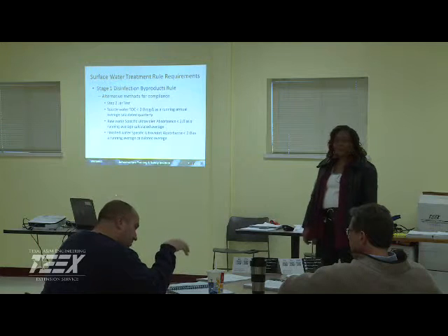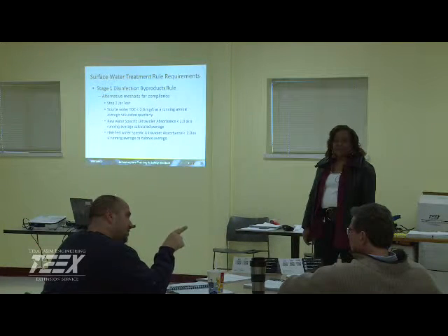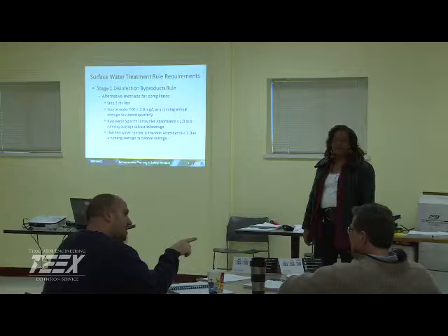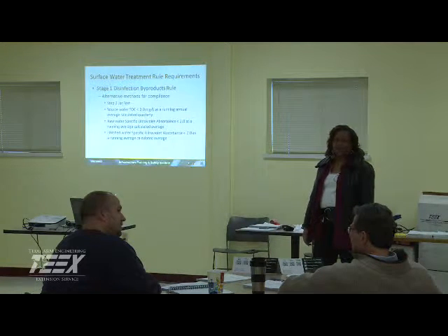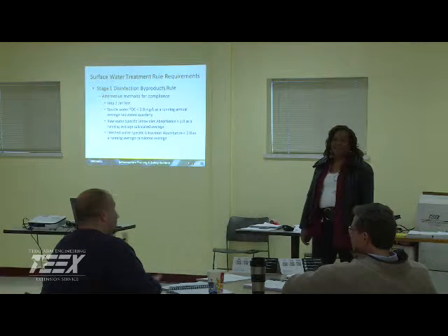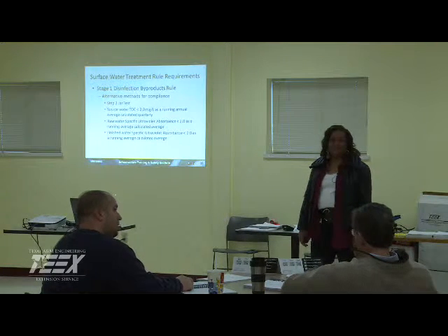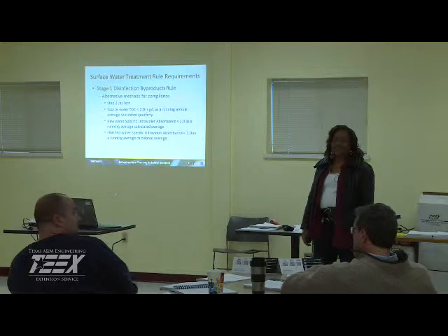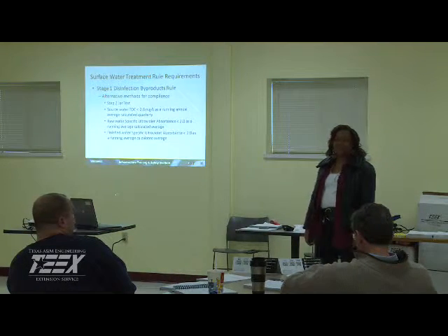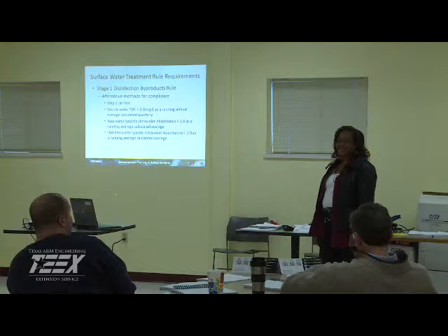Is that kind of like what we used to do with the lime additive? It's kind of like a basic jar test. You grab a sample and just make sure it's flocking and settling out, and look at the size, the clarity, all of that. You time it, you let it sit for a few minutes, but since we have the upflow clarifiers, it's not a traditional jar test. And we do the drawdown tests for our chemicals to see what we're pumping and how much. But our water is very consistent.